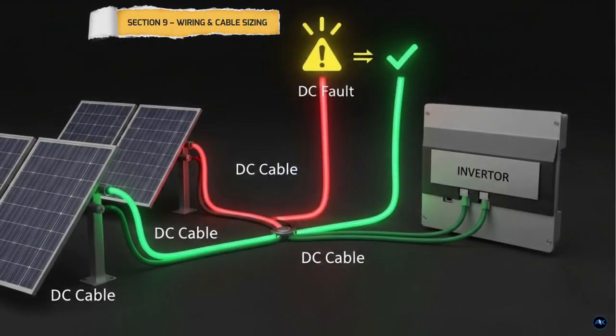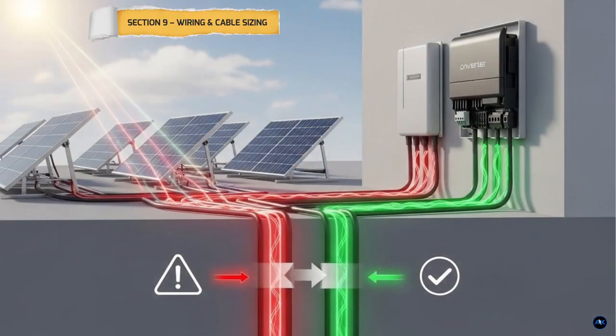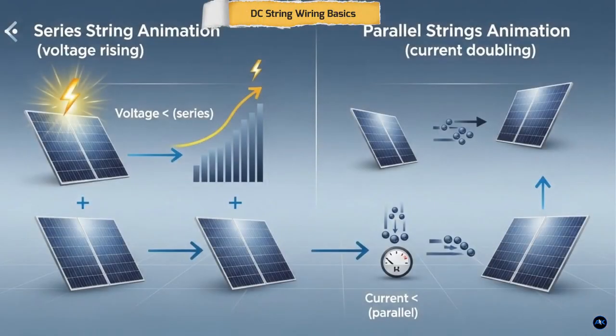You can design the perfect solar system on paper, but bad wiring can still cause power loss, overheating, or even fire. So now let's talk about DC wiring and cable sizing and how to do it safely. DC string wiring basics. Each solar string is wired in series to increase voltage. When strings are combined in parallel, the voltage stays the same, but the current increases. This is why cable sizing is based mainly on current, not power.